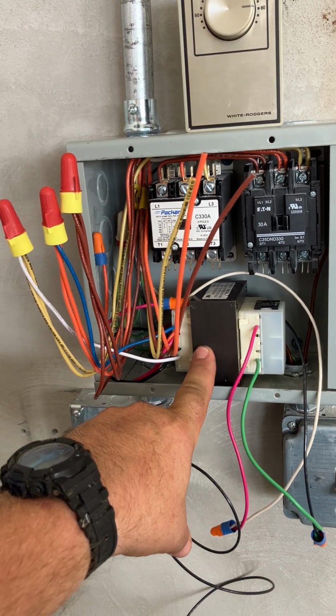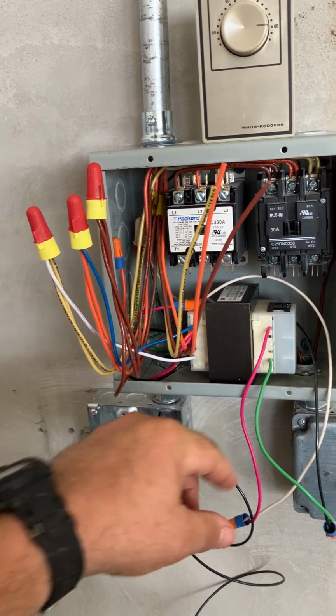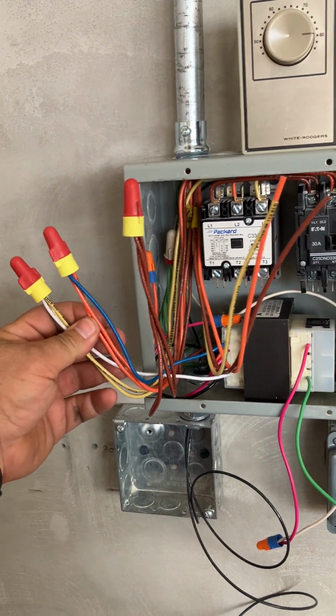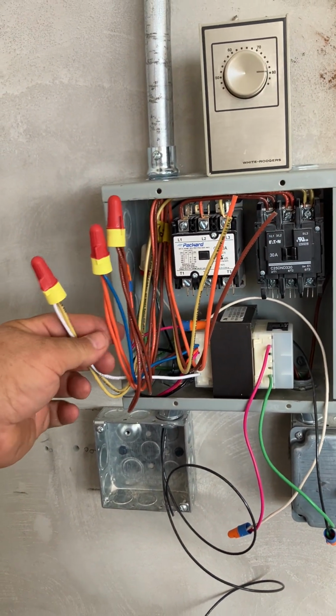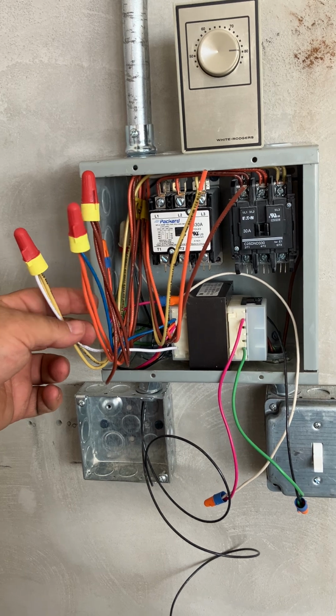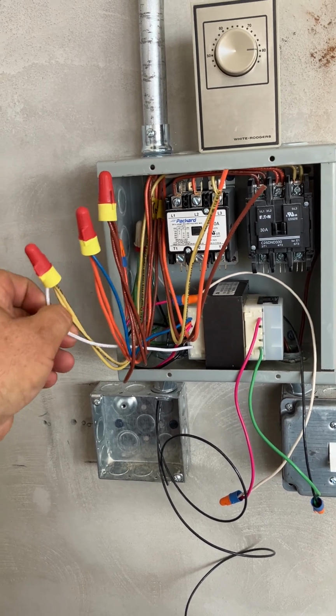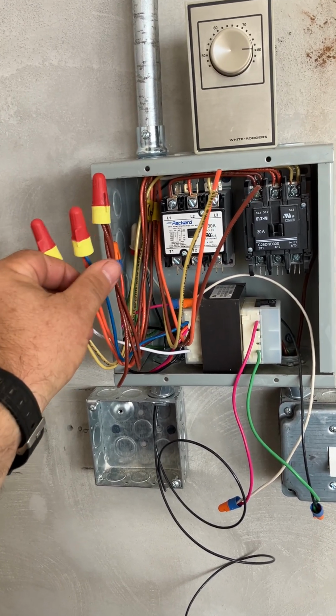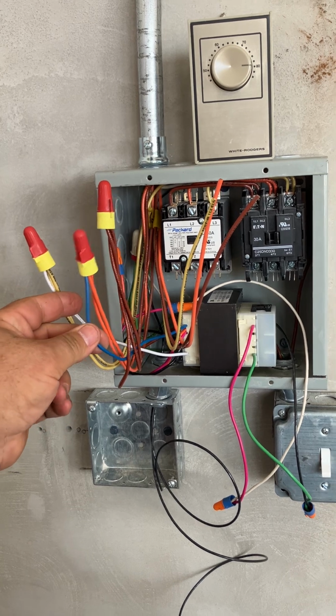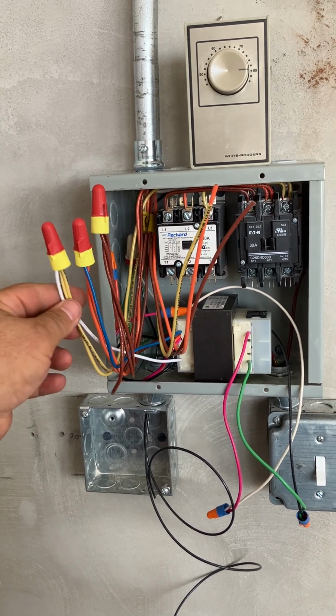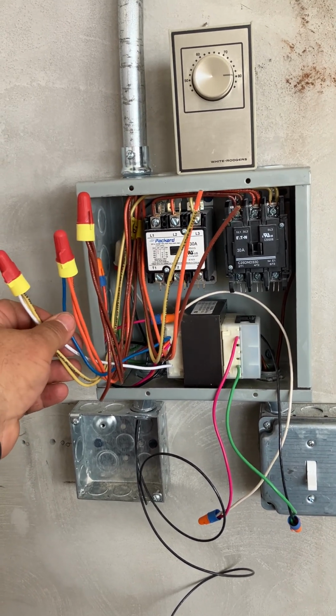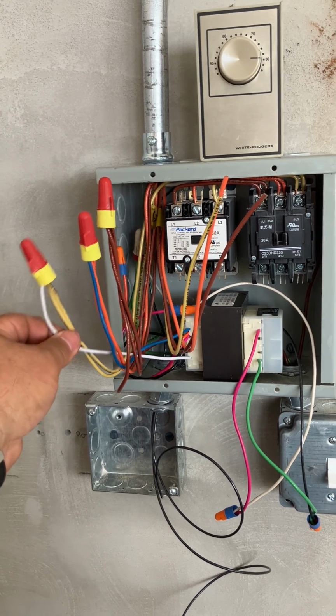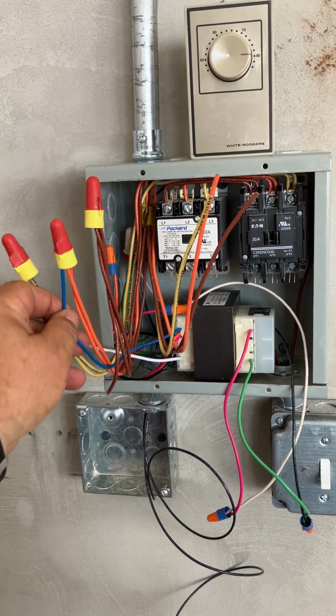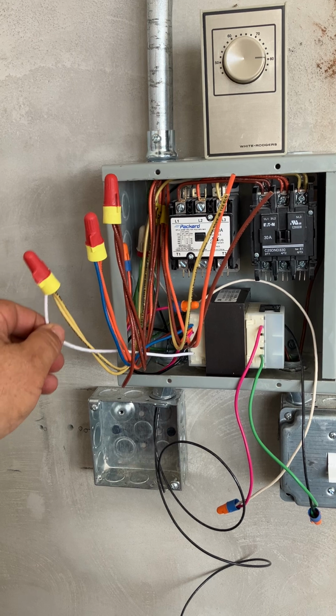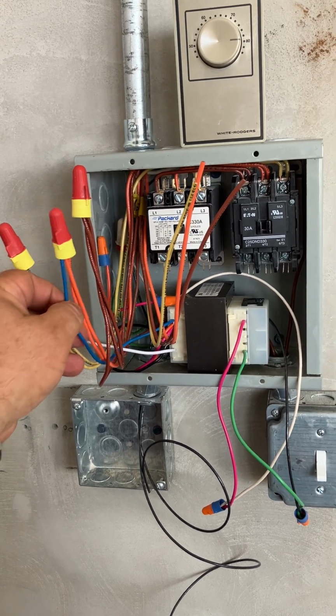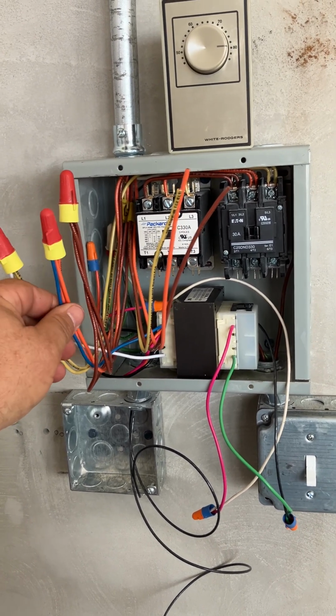And right here you see a transformer, a 480 volt to 24 volt transformer. And you can see that I have fed it off of two legs of the 480 volt circuit, single phase. Two legs off 480 is 480 single phase, right? So here's one wire, here's another. If I remember correctly, the white is the common for this transformer, and the blue is the 480.